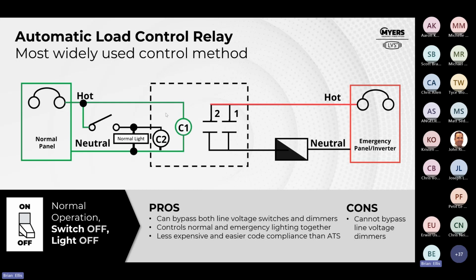So electrically, it's opposite. Now I can take my switch from the emergency switch leg side over to the utility side. That allows me to not only provide power to my normal lights, but every time there's power on the coil of a normally open relay, it closes. It does the opposite, right? So now the emergency light is following the switch and the normal lights. They look like they're in the same zone, even though this utility power is never powering this emergency light.